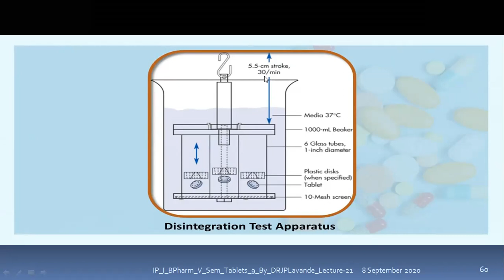You can see this is the diagrammatic representation of the disintegration test apparatus. This is the tube 1, 2, 3, in the vertical section view. Here there is a mesh, the 10 mesh screen. This is the tablet, and this is the plastic disc placed above the tablet. The plastic disc is placed because when the basket moves in the up and downward direction, it gives an impact which simulates the in vivo system. These are the glass tubes, 1, 2, 3, and again 3 on that side. This is the beaker with 1000 ml capacity containing the media, either simulated media or water, and the temperature to be maintained is 37 degrees Celsius. Now this basket moves in the upward and downward direction over a distance of 5 to 5.5 centimeters, at 30 strokes per minute.